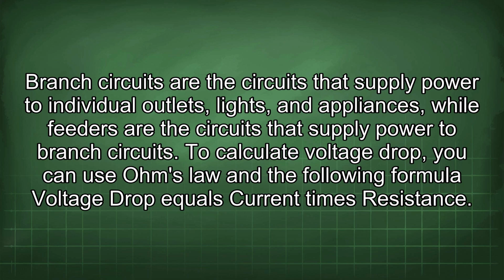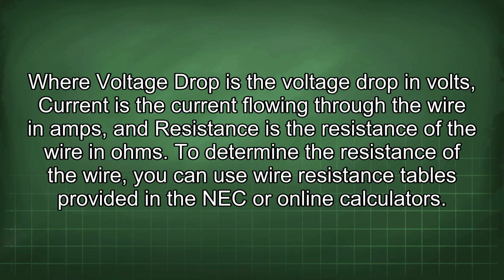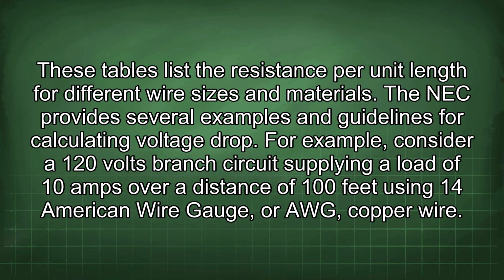To calculate voltage drop, you can use Ohm's law and the following formula: voltage drop equals current times resistance, where voltage drop is the voltage drop in volts, current is the current flowing through the wire in amps, and resistance is the resistance of the wire in ohms. To determine the resistance of the wire, you can use wire resistance tables provided in the NEC or online calculators. These tables list the resistance per unit length for different wire sizes and materials. The NEC provides several examples and guidelines for calculating voltage drop.